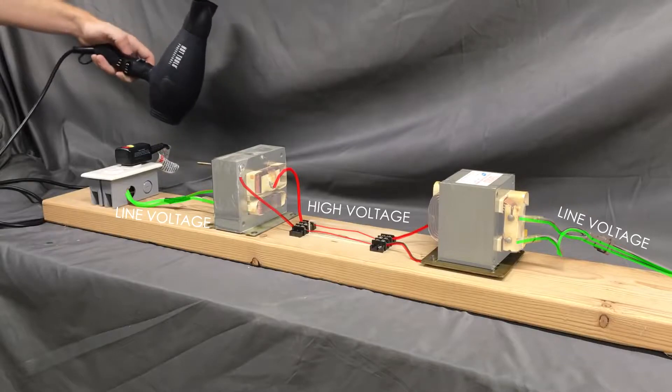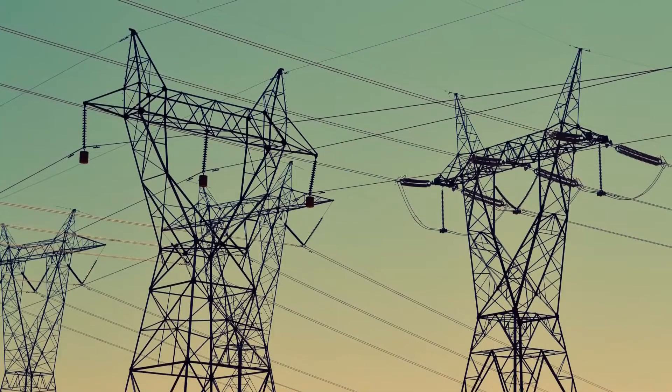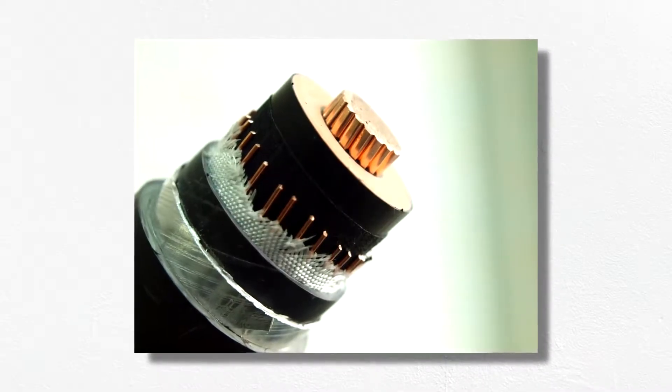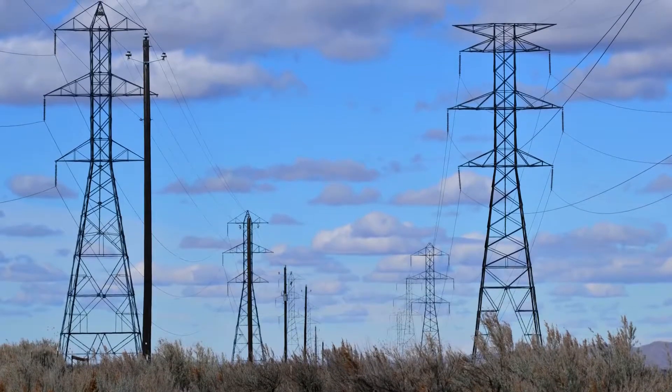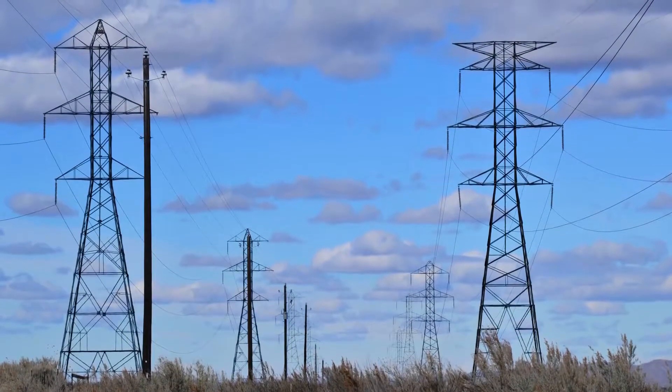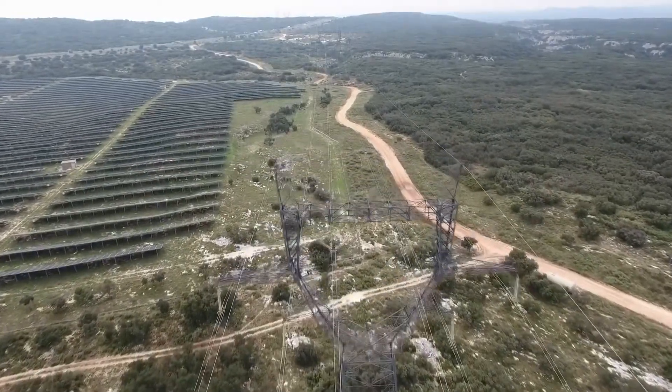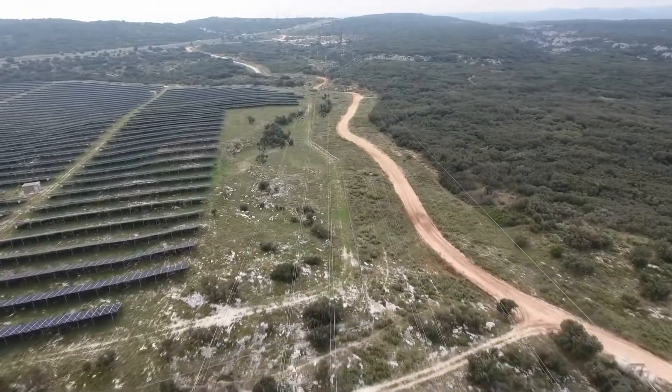What we've also done is make things much more dangerous. You can think of voltage as electricity's desire to flow. High voltage means that the power really wants to move and will even flow through materials we normally consider non-conductive, like air. The engineers designing high voltage transmission lines have to make sure the lines are safe from arcing and other dangers. Most long-distance power lines don't use insulation around the conductors themselves — insulating in this way would have to be so thick it wouldn't be cost effective. Instead, most of the insulation comes from air gaps, simply spacing everything far enough apart. Transmission towers and pylons are really tall to prevent anyone or any vehicle on the ground from inadvertently getting close enough to the conductors to create an arc.